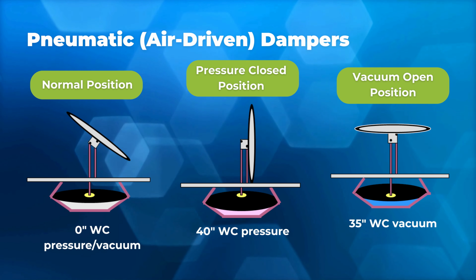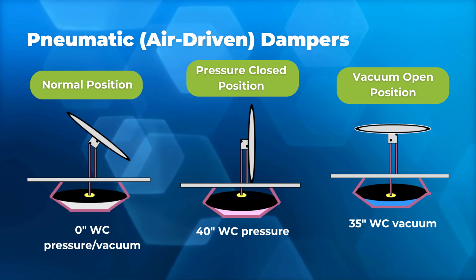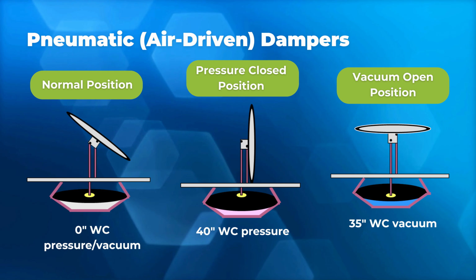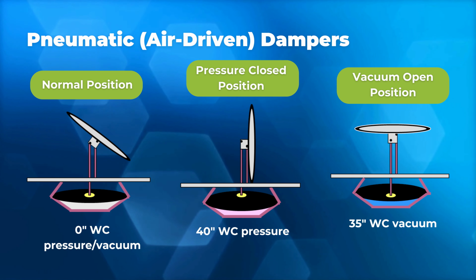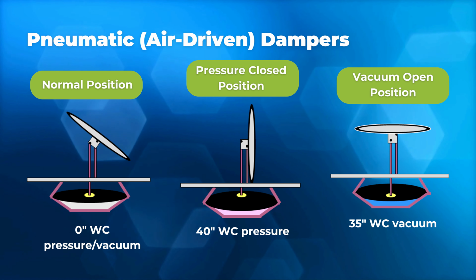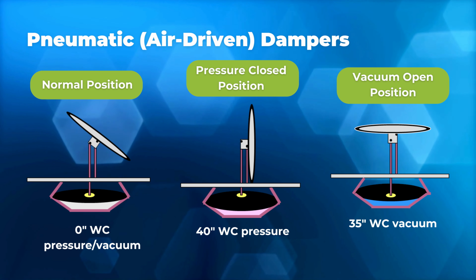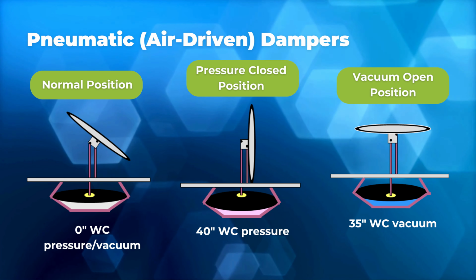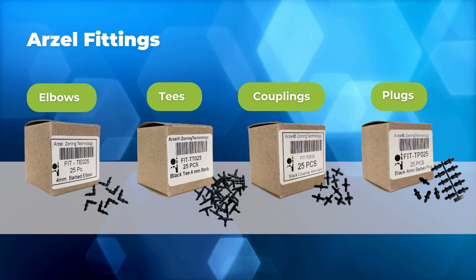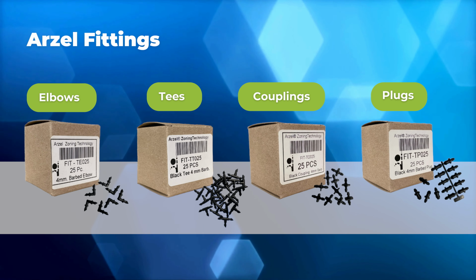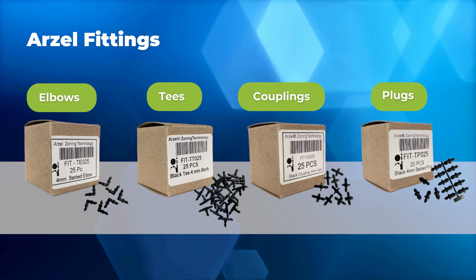And then with our dampers, they're pressure closed. It's going to be 40 inches of water column as your minimum number that you would look for to close our damper. And then they're vacuum open, and that's going to be at least a negative 35 inches of water column. So that's essentially what you're looking for with the dampers. And then we do offer a number of different fittings as well to make installation easier for you guys.